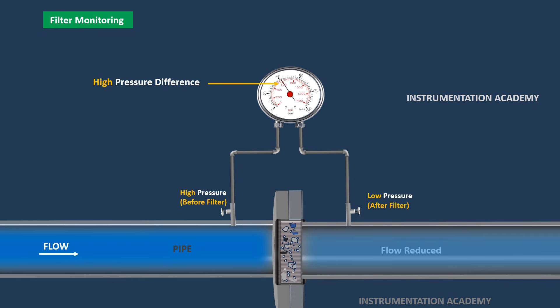When the differential pressure exceeds a predetermined threshold, it signals that the filter is clogged and needs servicing. This allows operators to take timely action, preventing contaminants from bypassing the filter and ensuring that the system continues to operate efficiently.